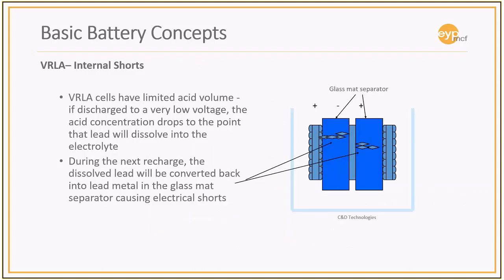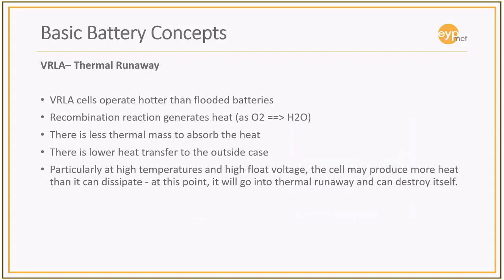Internal shorts, we talked a little bit about that with flooded cell batteries, but it happens with valve regulated as well, where you get plate growth that goes through the separators and ends up shorting those plates out. Thermal runaway: as these batteries get warmer during discharge, it generates O2, which eventually turns into H2O, and there's less thermal mass to absorb the heat, so you get higher and higher temperatures. Thermal runaway is something that will destroy the batteries, and violent failure and potential fire can result.